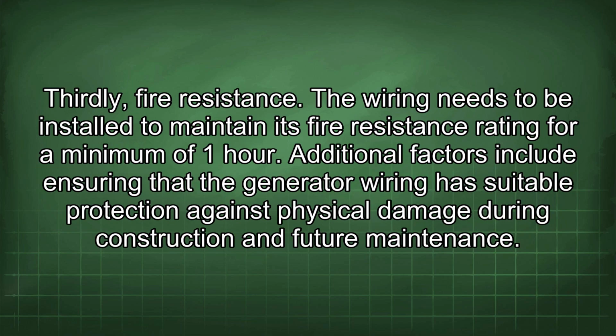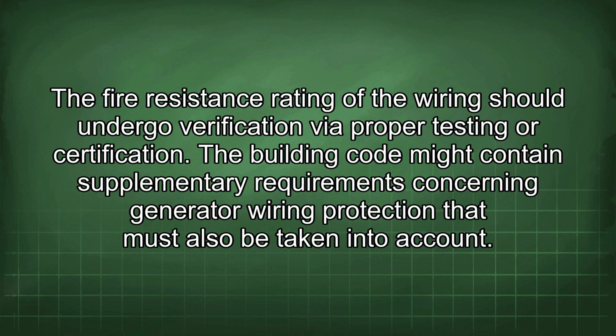Thirdly, fire resistance. The wiring needs to be installed to maintain its fire resistance rating for a minimum of 1 hour. Additional factors include ensuring that the generator wiring has suitable protection against physical damage during construction and future maintenance. The fire resistance rating of the wiring should undergo verification by proper testing or certification. The building code might contain supplementary requirements concerning generator wiring protection that must also be taken into account.